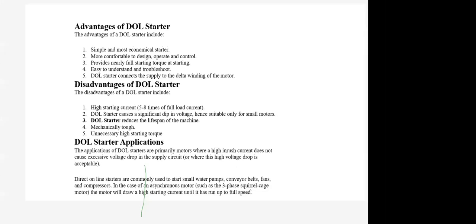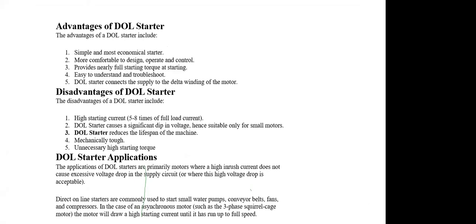As I said, this direct online starter is my favorite starter, and it's always very simple and economic, easy to understand and troubleshoot. And there's a 3-lead connection, that is also important, whereas in case of star delta you need a 6-lead, which of course has a lot of disadvantages. As I said, it is a limited application, normally only up to 7.5 HP, and of course if it is 6 times the full load current, there will be a sudden, significant dip in voltage. That's why it is suitable for small motors.